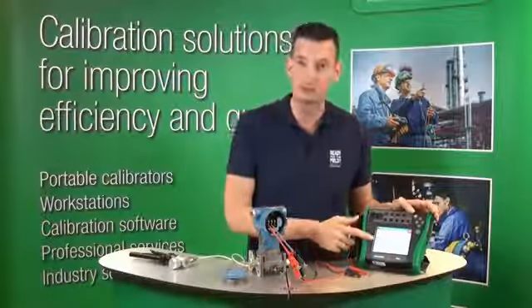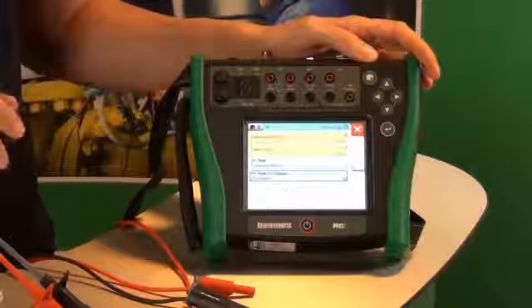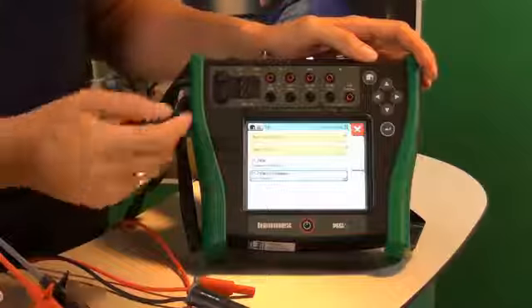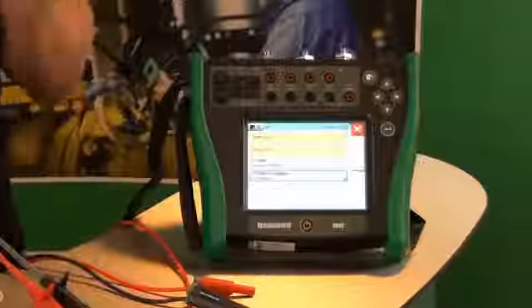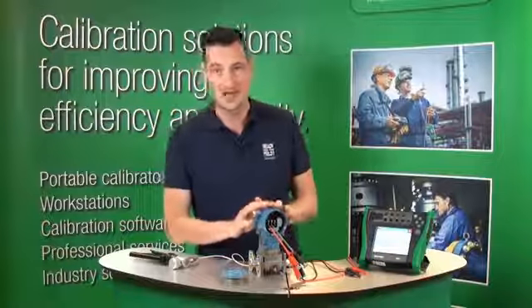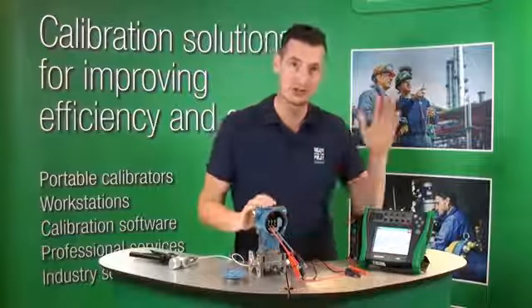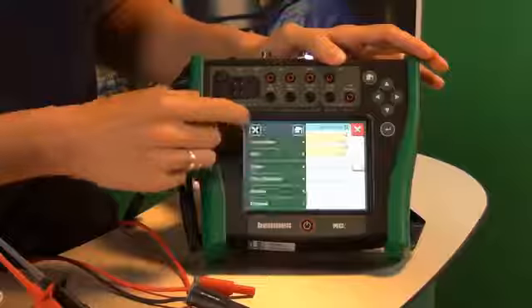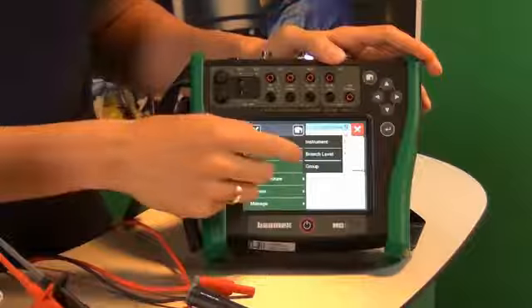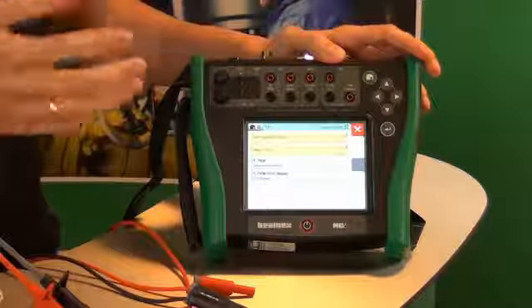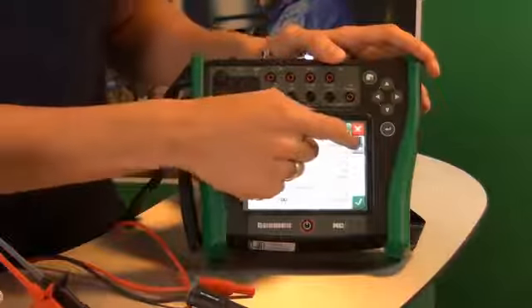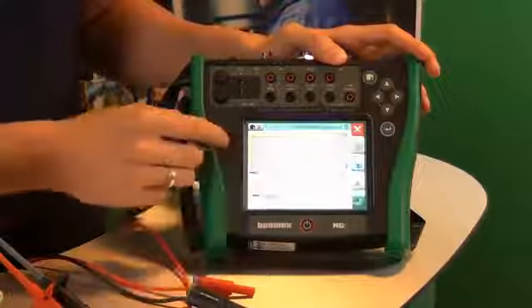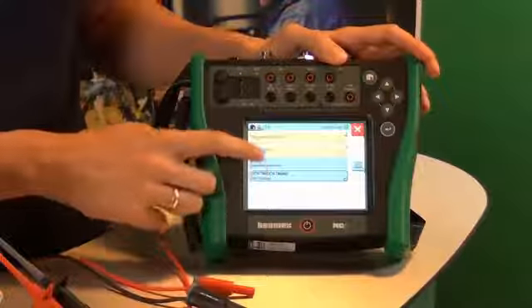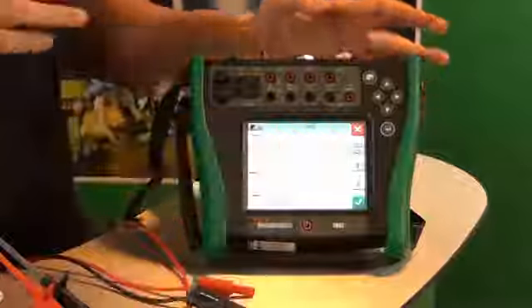As you can see, I've got two pre-programmed instruments there. All I have to do is create a group, because we're going to calibrate this milliamp analog output as well as the control room digital display. So we create a new group and add those two instruments to it — click on the first one, add it to the group, and the second one as well. You can see there are two highlighted that are part of that group.